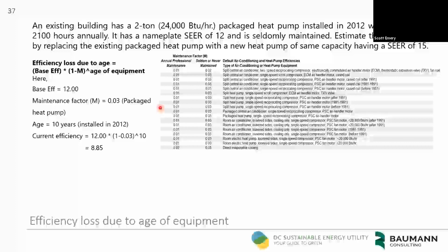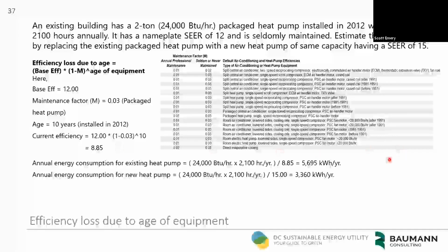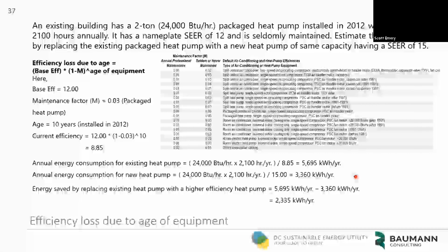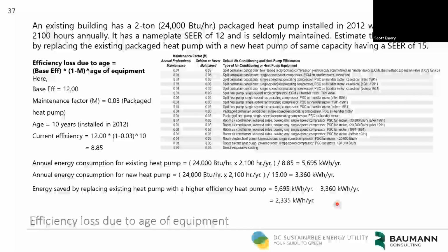and that's your table. And then here we go with a base efficiency of 12 SEER with the maintenance factor of 0.03, and the age is 10 years installed. The current efficiency would be, rather than 12, 8.85. So your annual consumption, if you do all the calculations across there, is going to be 5,695 kilowatt hours per year. Now your new heat pump will only consume approximately 60% of that, so it's 3,360 kilowatt hours per year. Energy saved by replacing the existing heat pump with a higher efficiency heat pump will be a total of 2,335 kilowatt hours per year.